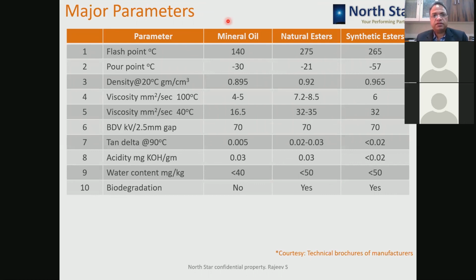If you look at a comparison of major parameters of the three insulating liquids, this is a very interesting comparison. Flash point, which is responsible for the equipment catching fire: for mineral oil it is 140 degrees centigrade, for natural esters it is 275, and for synthetic esters it is 265. Pour point, which is very important for flowability of the liquid at lower temperature: mineral oil is minus 30, natural ester is minus 21, and synthetic ester is minus 57. So if pour point is concerned, synthetic esters are the best suited, meaning even at minus 57 degrees centigrade, they will remain liquid and you can pour them.